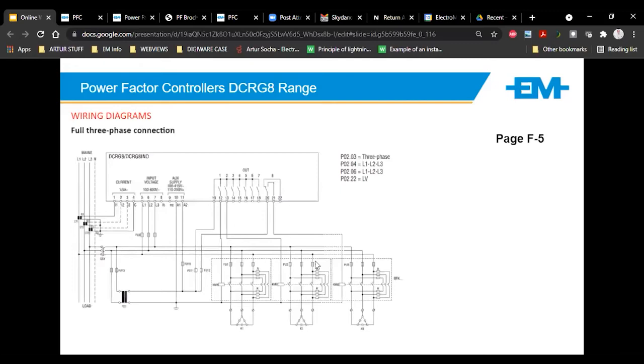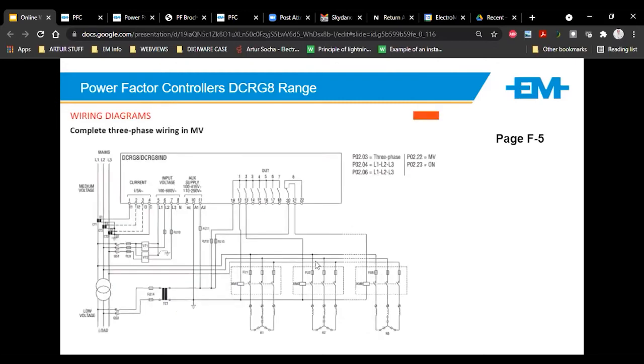And the DCR-G8 is a true complete 3-phase measurement device, preferably 3 CTs to measure each phase, and then it would bring in the steps, let's call it more accurately than a single phase measurement device. There's still a lot of controllers out in the market that just do single phase measurement. I'm not big on that. I would say DCR-G8, 3-phase measurement, so you know exactly what's happening on each phase. It can also be applied on MV solutions. So I would measure on the MV side via VTs, but I would correct on the LV side.